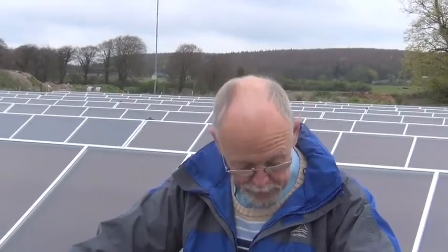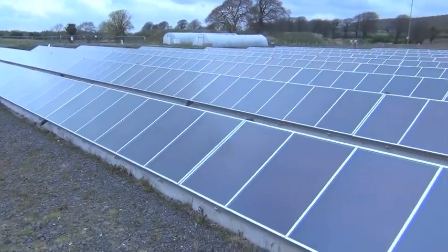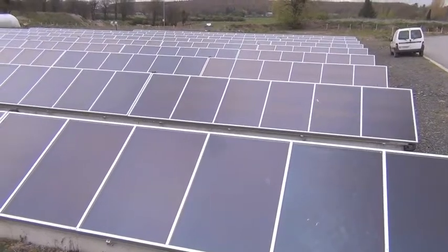We certainly have quite a few lessons of experience on this solar array. One is that there was no thought given at the design stage to phasing it for the ecovillage being incomplete. So we do now have a significant potential problem. If we have a heat wave and several days of sunshine in succession and all our hot water storage is up to maximum temperature, what do you do with it? You don't want to be dumping the heat in some way. One way to do it is to reverse the flow and pump hot water through the panels at night and release the heat to the night sky. Because if the glycol overheats, it begins to decompose. This is a problem quite a lot of domestic systems have — people don't realize it when they go away in the summer and their system is not designed to dump excess heat.